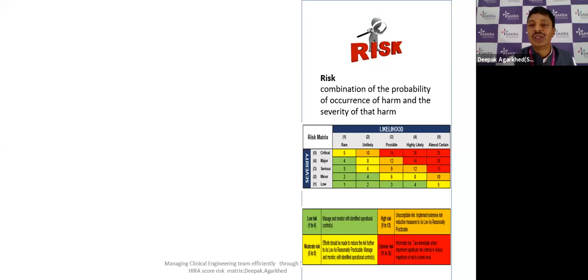In clinical engineering, I would like to take a few examples so that you can understand what I am trying to tell you. For example, the equipment, as I told you, can be divided into three: soiled equipment, visibly contaminated or very likely to be contaminated, and devices which are not contaminated. Now let us talk about visibly contaminated. Let us take, for example, a suction apparatus, a suction jar where the suction happens. If the suction unit with the jar comes to the clinical engineering department without proper cleaning, what may happen? There is a severity.